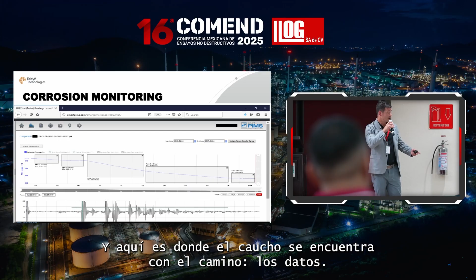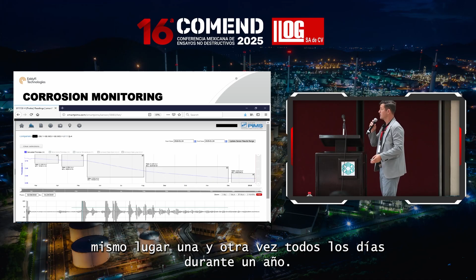This is where the rubber meets the road, the data. Thickness is on the y-axis and time is on the x-axis. Over the course of a year, this is a trend line of daily thickness readings. That sensor wakes up and takes a reading at the same place over and over, every day for a year, plotting what's happening over time.